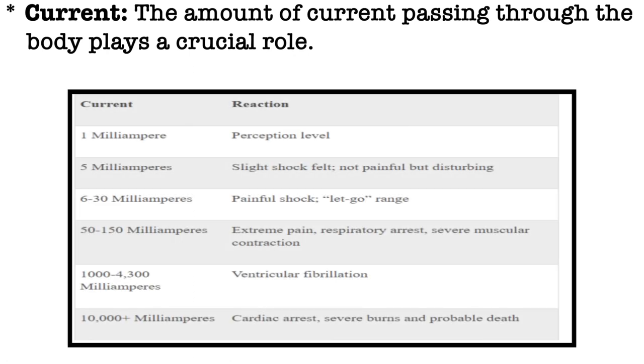Regarding current — the amount of current passing through the body plays a crucial role; higher current is more likely to cause serious harm. At roughly 1 milliampere, the effect is perception level only. At around 5 milliamperes, there is a slight shock felt — not painful but disturbing. At 6 to 30 milliamperes, there is a painful shock. At 50 to 150 milliamperes, extensive pain is felt. At 1000 to 4300 milliamperes (1 to 4.3 amperes), there are serious effects that may cause death.